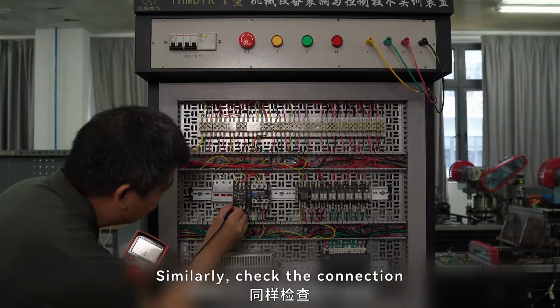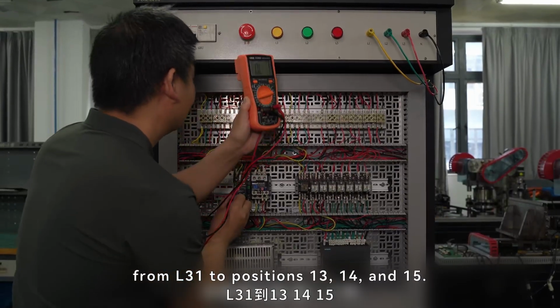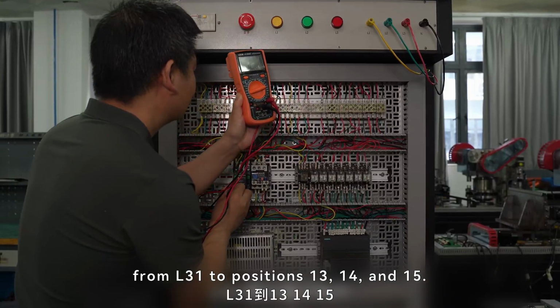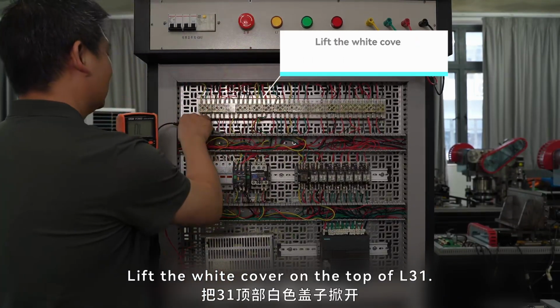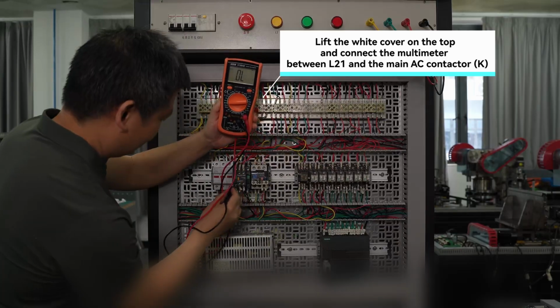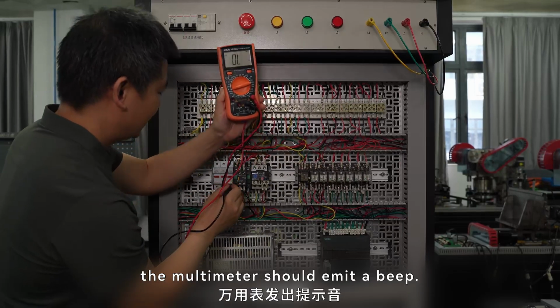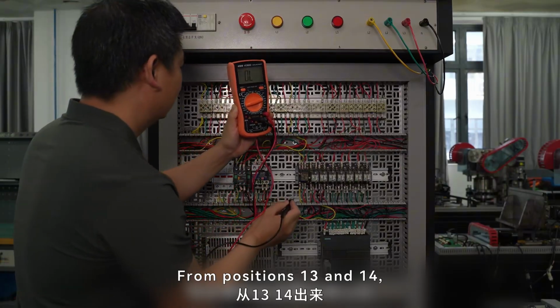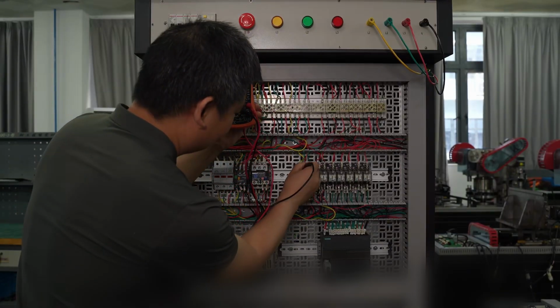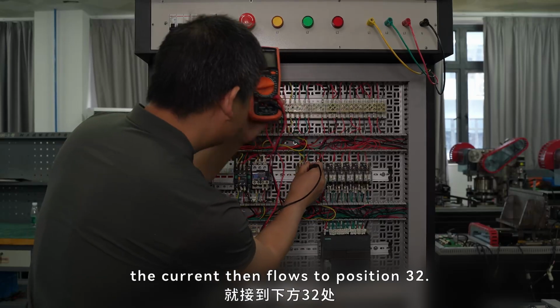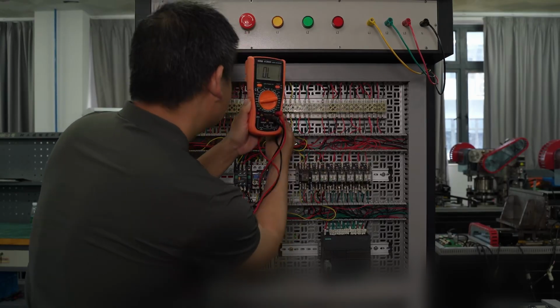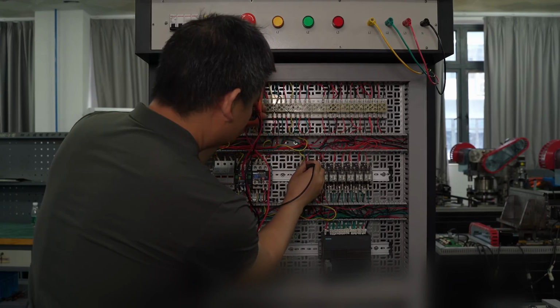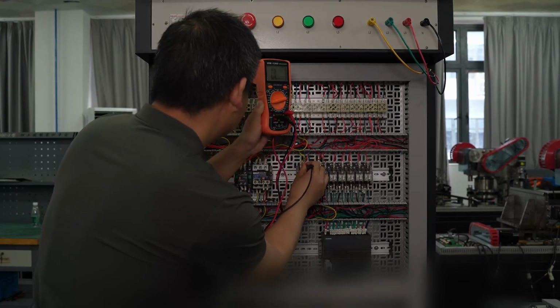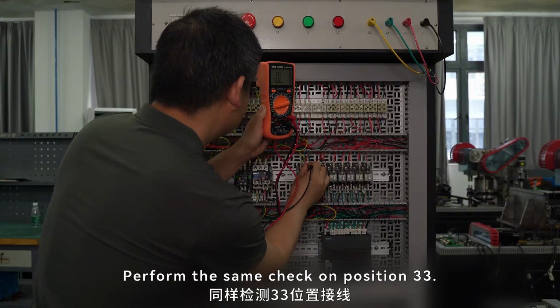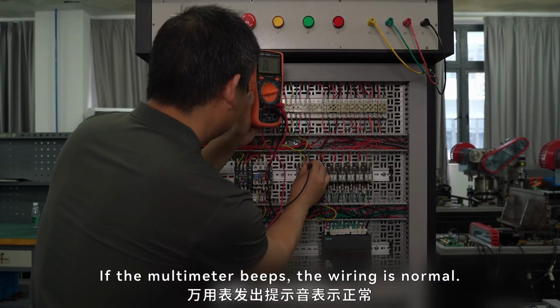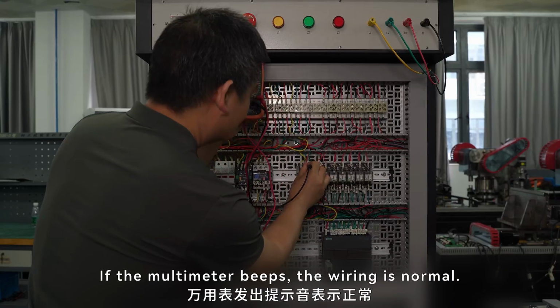Similarly, check the connection from L31 to positions 13, 14, and 15. Lift the white cover on the top of L31. When current flows to the positions, the multimeter should emit a beep. From positions 13 and 14, the current then flows to position 32. Perform the same check on position 33. If the multimeter beeps, the wiring is normal.